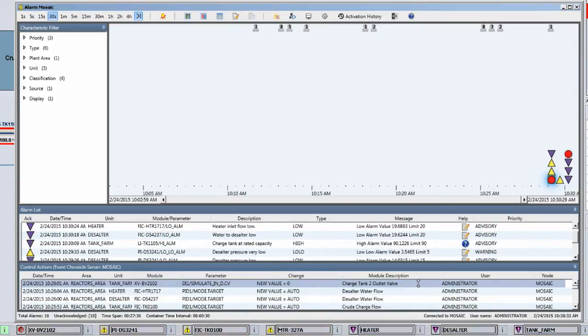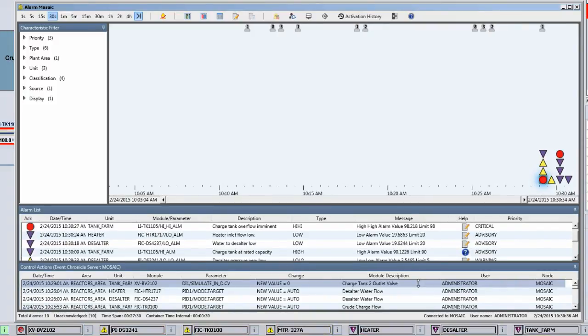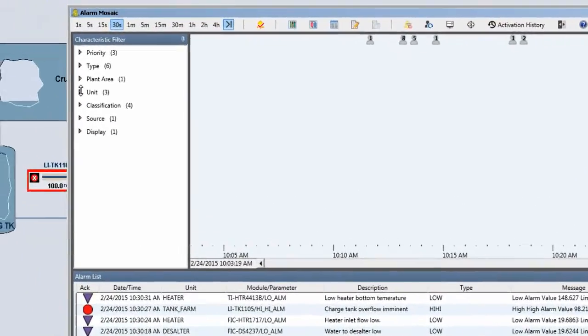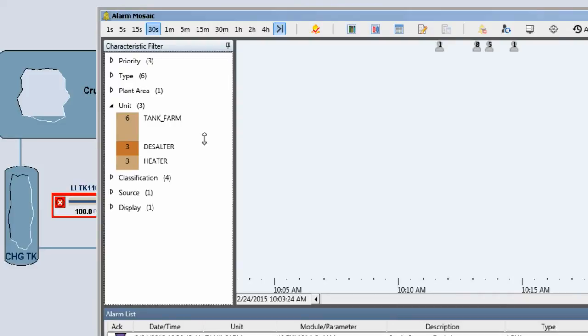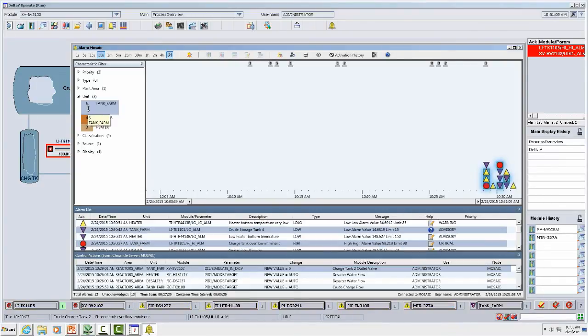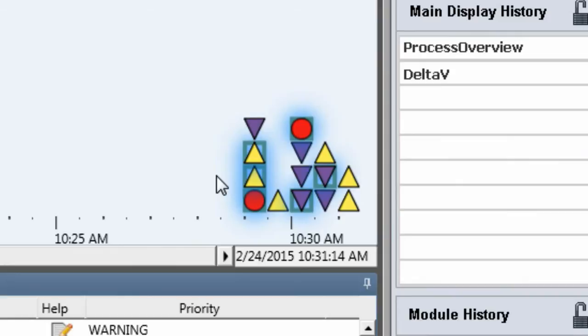It's quite typical for the operator to want to first rule out operator action before going on to other possible alarm cause considerations. Now that we have a good number of alarms occurring, let's use the characteristic filter to understand this alarm pattern. The first thing I'm going to do is look at how these alarms spread across the plant. I see that six alarms occurred in the tank farm — the greatest number — three in the desalter and three in the heater. If I highlight a particular unit, in this case the tank farm, you get a corresponding highlighting of the alarms in the iconic area.